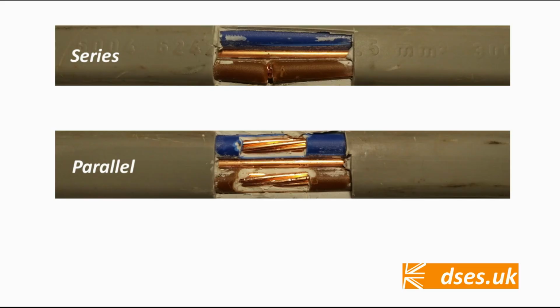But what's the use of an AFDD on such low current circuits like smoke alarms or even lighting with today's efficient LED lamps fitted throughout? At 230 volts, the current is too low for a series arc to form. You need to be pulling a good couple of amperes or so to get these things to trip, and my loading isn't that. While parallel arcs are still technically possible, a line neutral or line earth arc will likely operate an RCBO in a timely enough fashion, I'm sure.